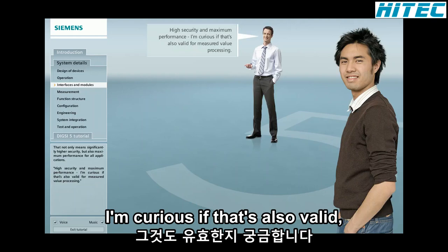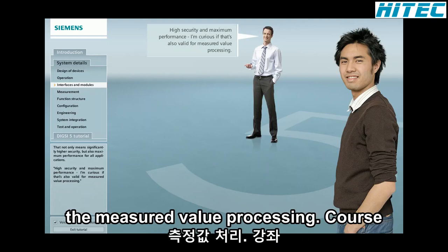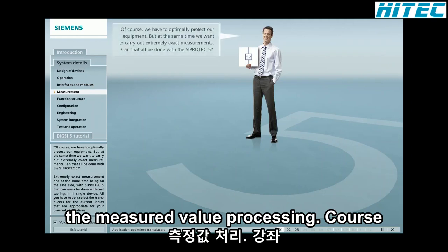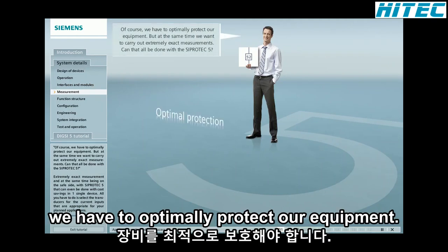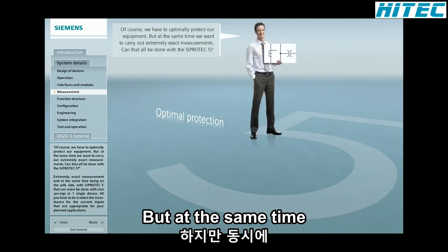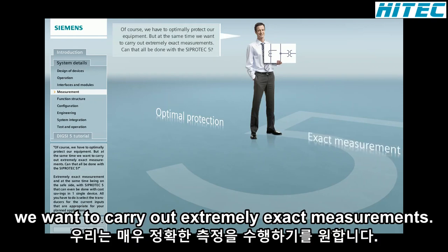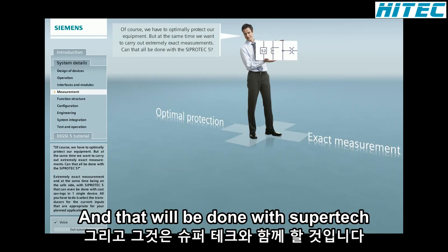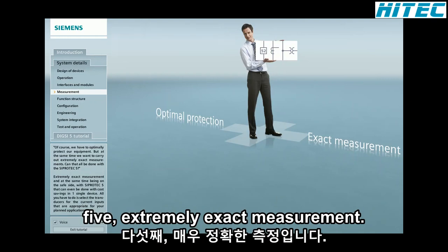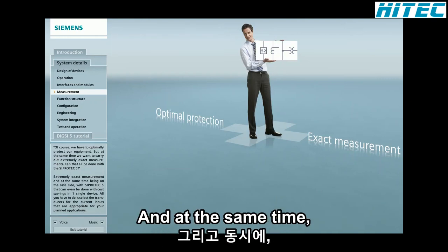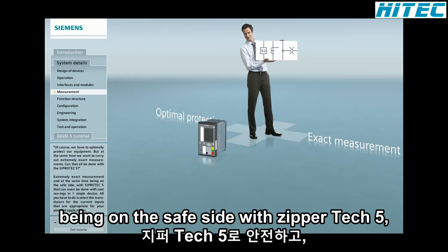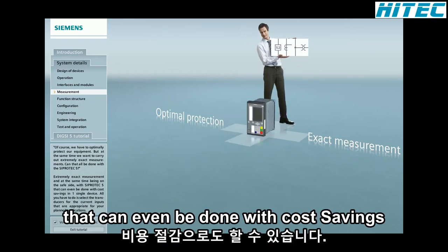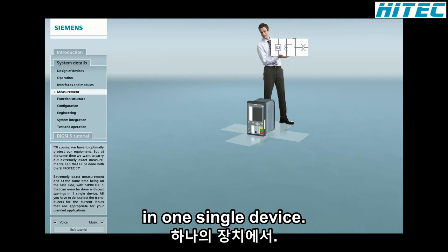I'm curious if that's also valid for measured value processing. Of course, we have to optimally protect our equipment. But at the same time, we want to carry out extremely exact measurements. Can that all be done with SIPROTEC 5? Extremely exact measurement and at the same time being on the safe side, with SIPROTEC 5 that can even be done with cost savings in one single device.